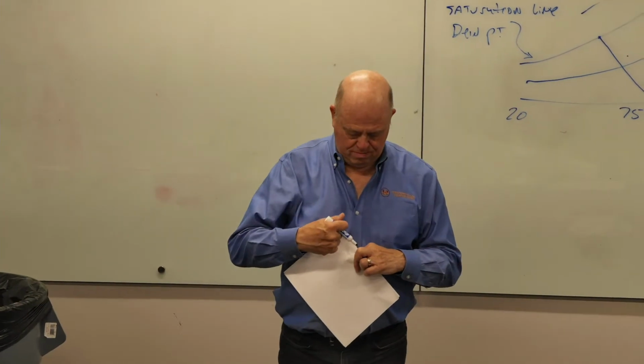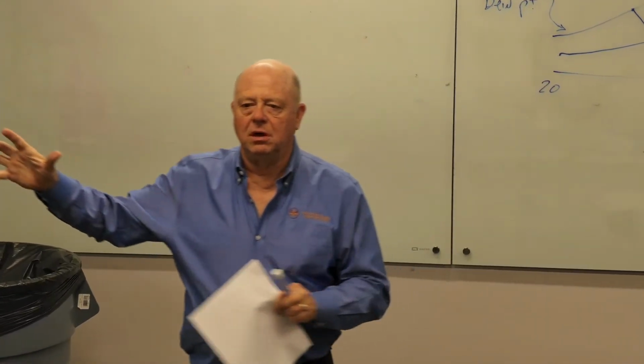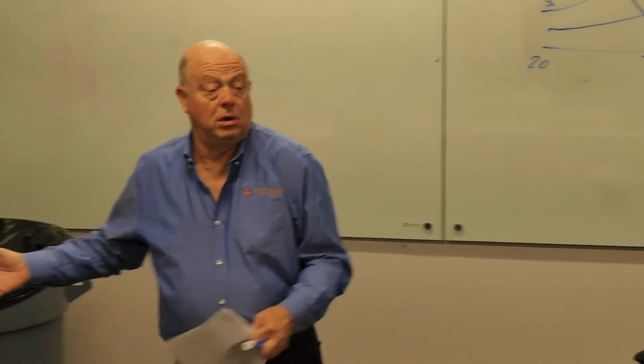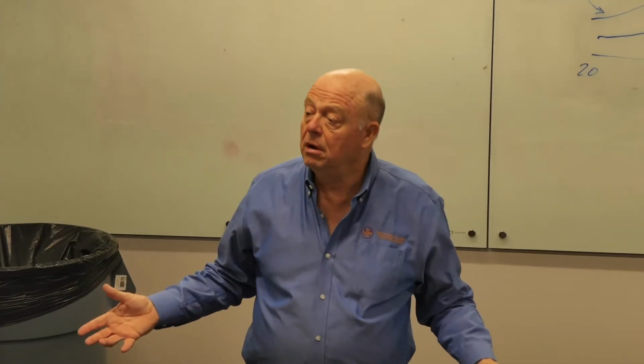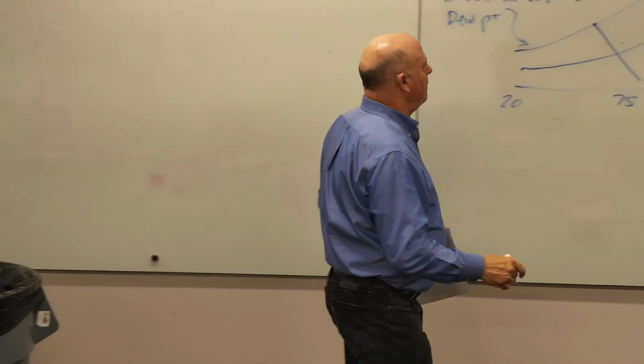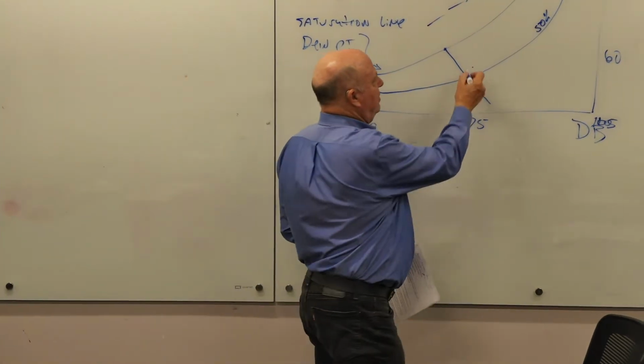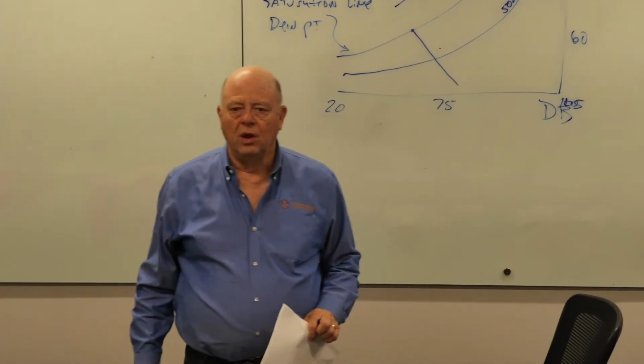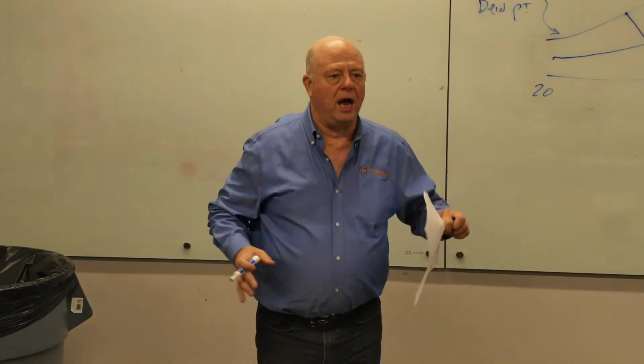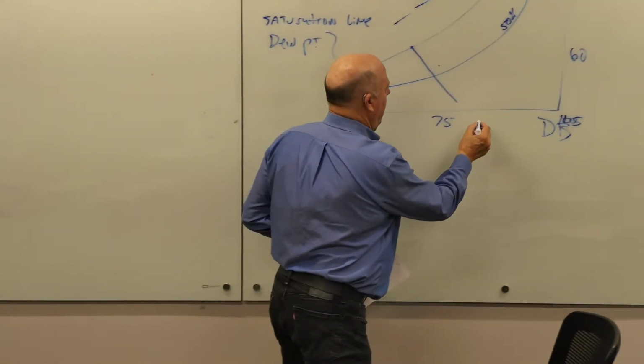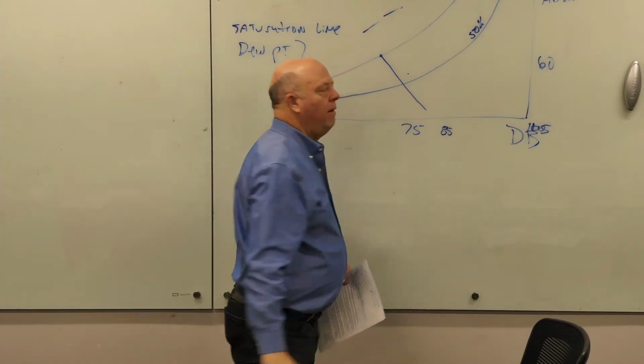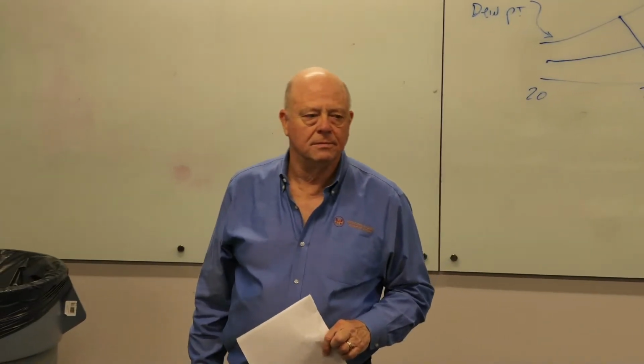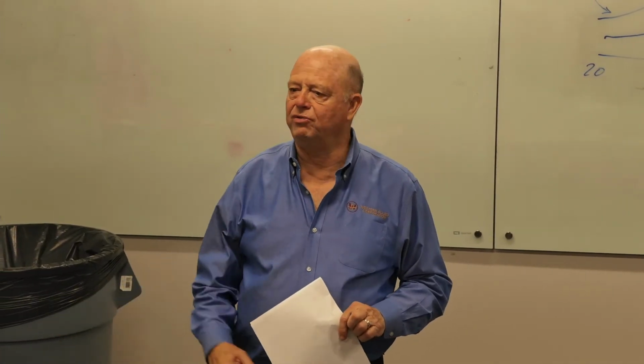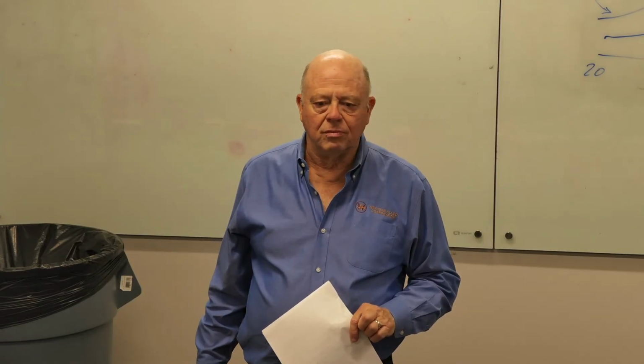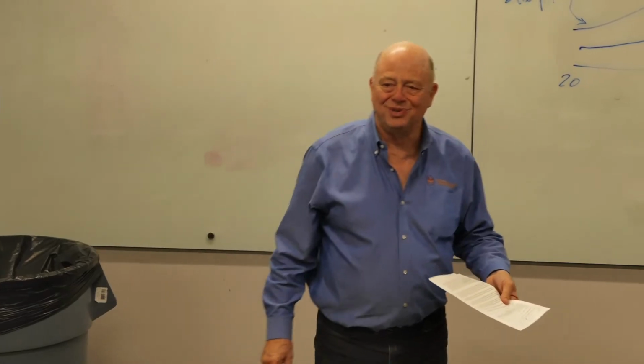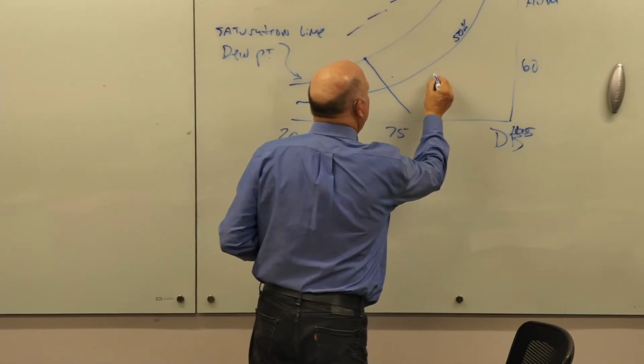So let's talk about the weather for a minute. Unless a new front comes in bringing more moisture, or it's a Santa Ana bringing in drier air, if you walk out and get in your car at 75 degrees and 60 grains, then take a walk around 10 o'clock and it's now 85, how many grains will be in the air? Assuming no weather front change, it's still 60 grains—it hasn't changed. So now you're going to be here.